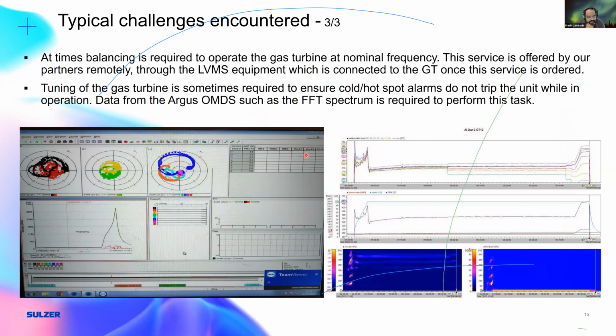It's not always that easy. When you start a gas turbine, certain things could be amiss and you might need to balance it. We connect what we call the LVMS equipment - a Pelican case with a computer and screen that collects all the vibrations from the bearings, with a remote connection to our partners who give us recommendations on how best to balance the turbine, telling us where to introduce weights in which bearings, or where to take some out.